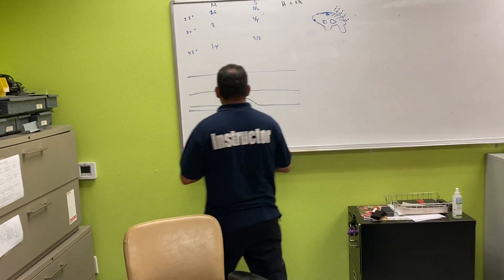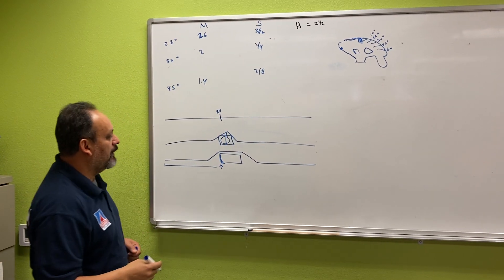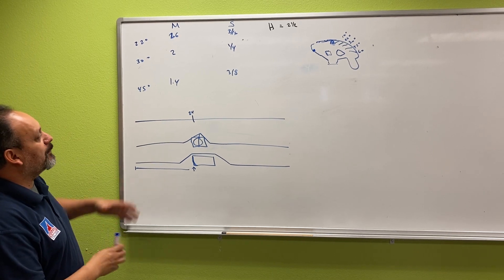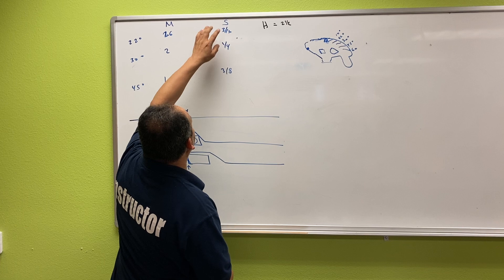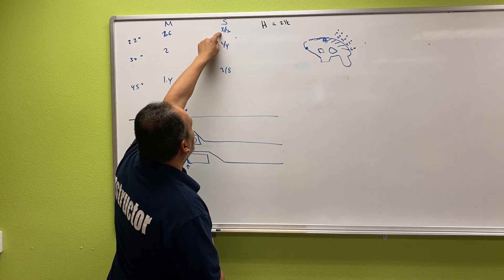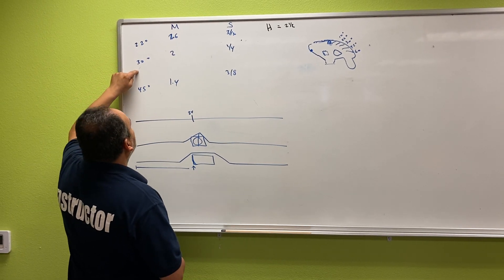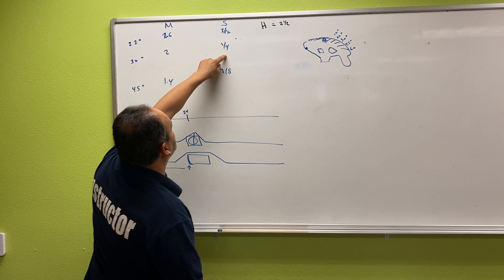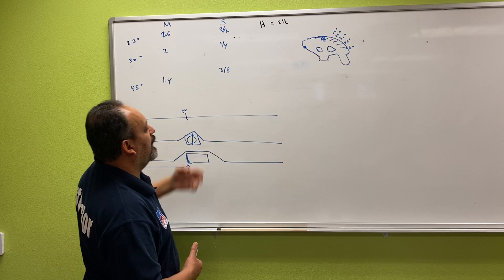Our distance is 24. We still have to do the same calculations and same principles apply. For a 22-degree bend, the multiplier is 2.6 and the shrinkage is three-sixteenths. For a 30-degree bend, the multiplier is 2 and the shrinkage is a quarter. For a 45-degree bend, the multiplier is 1.4 and the shrinkage is three-eighths.